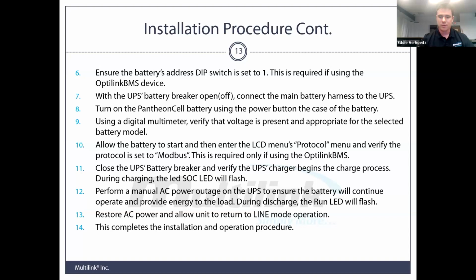So the battery breaker is closed in step number 11. We verify that the charger has begun. We can do so during the charging process. We can monitor the SOC, which stands for state of charge LEDs, to make sure that they are flashing.